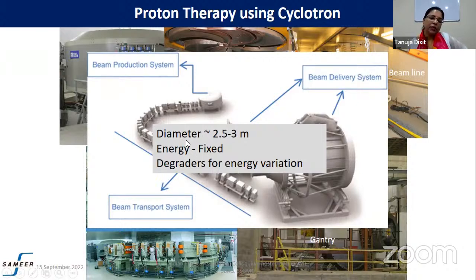Here you see that the diameter required is 2.5 to 3 meters to achieve protons up to 230 MeV energy, and the energy in the cyclotron is fixed. Therefore, to vary the energy to get the beam at different depths, degraders are used in the case of a cyclotron.